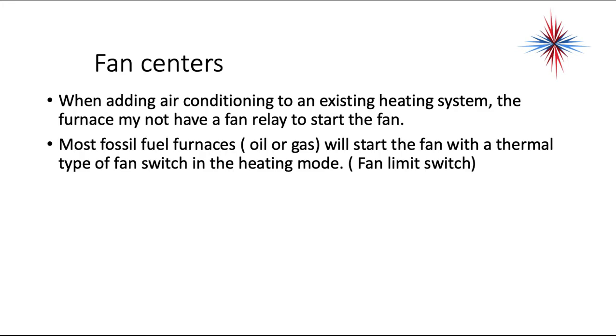Now, the reason we use a fan center is because in many cases, the original furnace wiring was not set up to add air conditioning. The furnace, oil or gas, will start the fan with a thermal type fan switch like the combo fan limit switch we talked about in a prior video, and it starts it in heating mode.